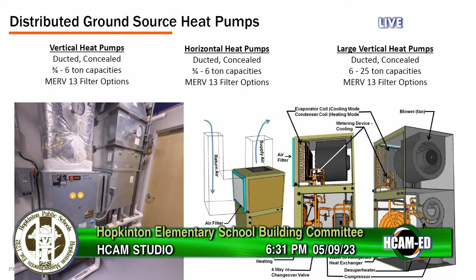I think the other part was the water loop itself. The temperature range of that geothermal loop is only from about the low 40s up to 95. It's a very small range, so you never get to the heated boiling levels that you get to in a boiler system, which is when a lot of those deposits start to come out of the water. In a traditional, old style heating system with a boiler, that water heats up to 180 degrees, which is very hot, which leads to a lot of expansion and contraction within piping systems. It leads to stresses and failures within piping systems. So you don't see as much of that fluctuation because the temperature band is very stable.